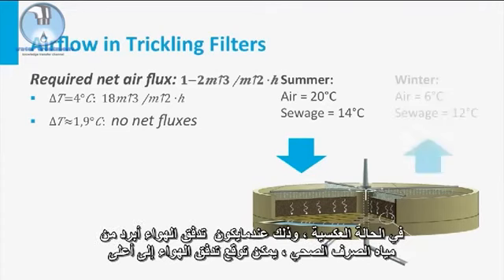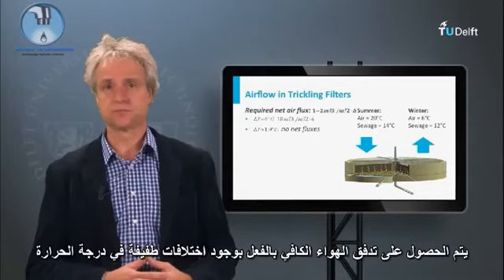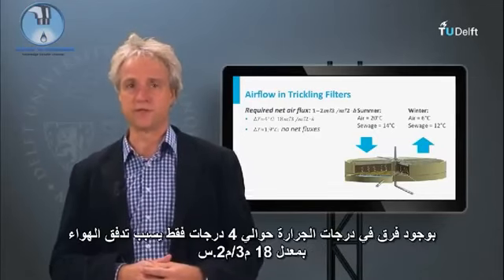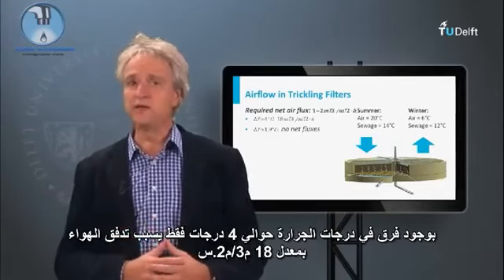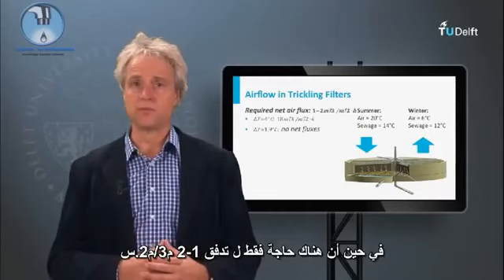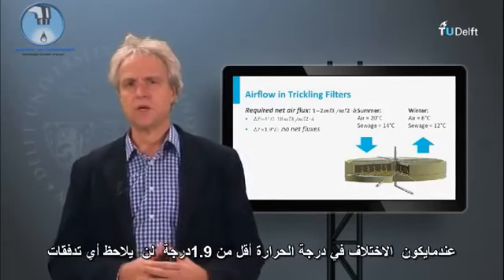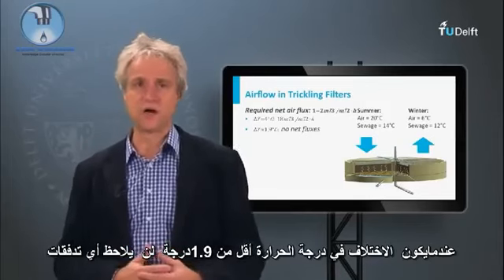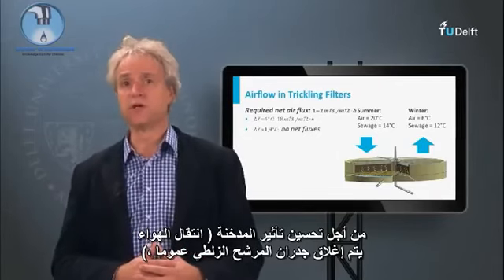In reverse situations, so when the air is colder than the sewage, an upward airflow can be expected and thus a more smelly trickling filter. Adequate airflow is already obtained with very little temperature differences. A difference of 4 degrees Celsius already causes an airflow of 18 cubic meters per square meter surface per hour, whereas only a flow of 1 to 2 cubic meters per square meter per hour is needed. When the temperature difference is less than 1.9 degrees Celsius, no net fluxes are observed. In order to enhance the chimney effect, the walls of a trickling filter are generally closed.